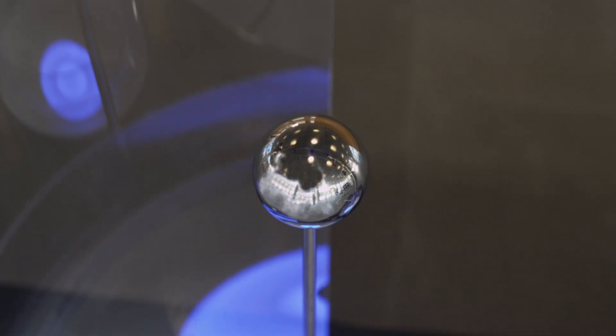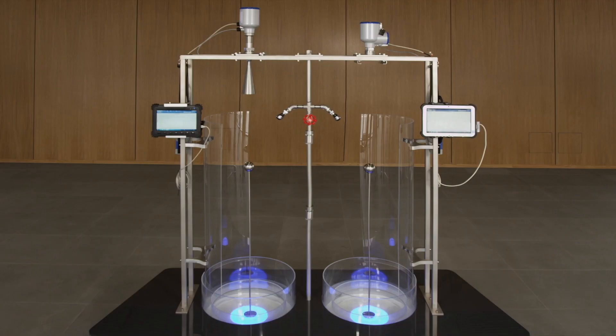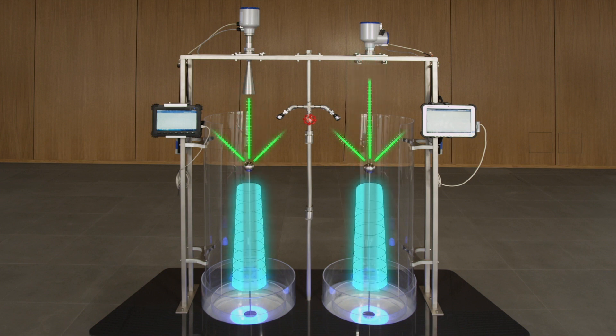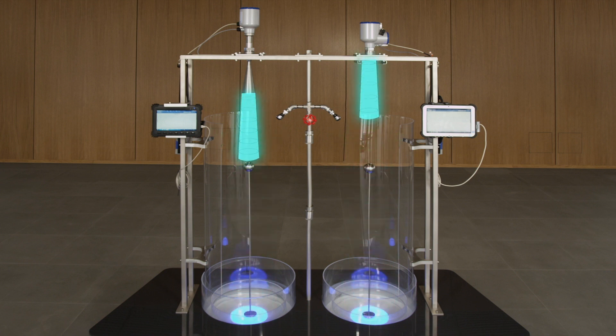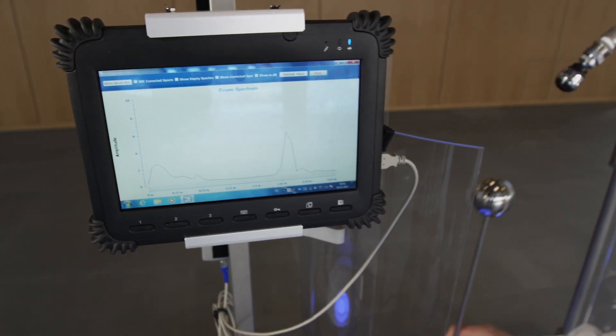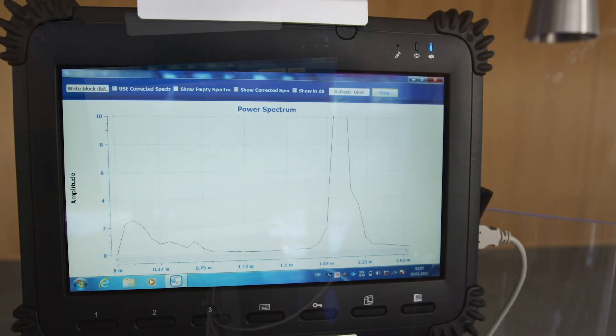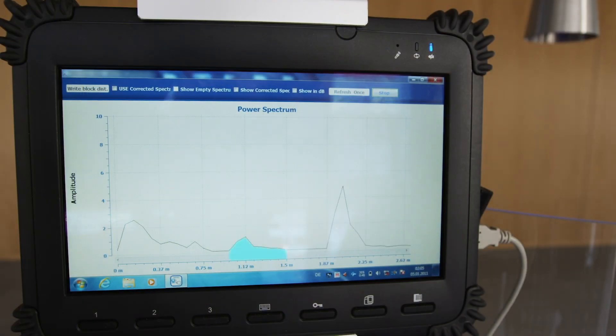A metallic sphere represents a conceivably weak reflector, since only a small part of the radiated signal is reflected back in the direction of the antenna. Thus, a sphere can be used to simulate reflections on products with a low dielectric constant, the so-called DK value. First, the metallic ball sphere is inserted under the 24 GHz device. In the spectrum recording, the reflection on the spherical surface is clearly recognizable.